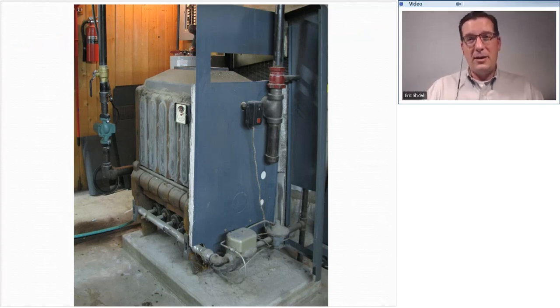One thing to notice, like I mentioned at the beginning of our class, the more you look at boilers, the more you'll find things that just aren't quite right. Here's a good example of that. There's a drip leg, a dirt leg, on the supply pipe leaving the boiler. And there's not a really good reason for that to be there. It serves no functional purpose. No one is ever going to pull that out and clean it. There shouldn't be any dirt leaving the boiler that you would want to accumulate. If you ever wanted to keep dirt out of the boiler, you would have to have that over here on the inlet side. But no, this is the supply side. This is the water leaving side. And there's a dirt leg there. It's just one of those interesting things that kind of make you go, hmm. And you're going to see these. The more you look, the more you're going to find them.